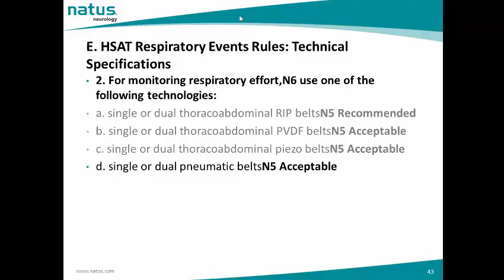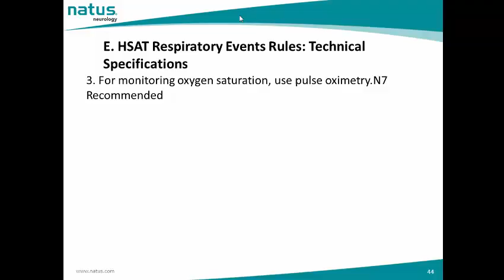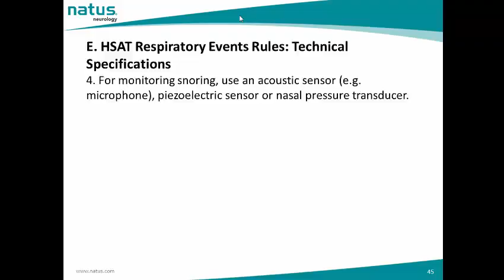For monitoring oxygen saturation, use pulse oximetry. The recording device should meet the same requirements for oximetry as the in-lab PSG. For snoring, use an acoustic sensor, piezoelectric sensor, and snoring that is derived from the nasal pressure transducer.